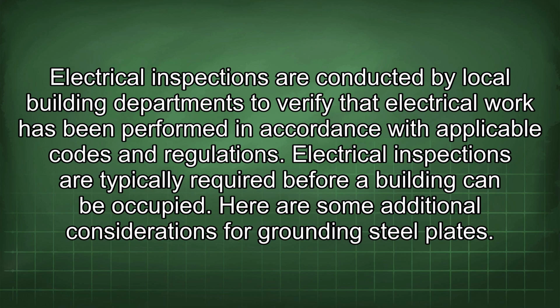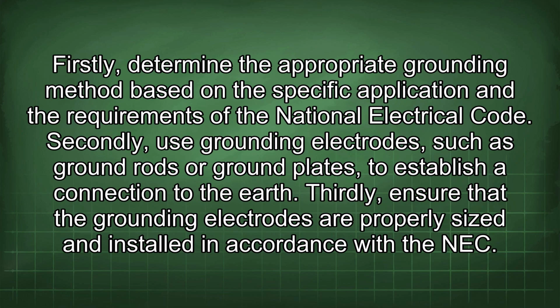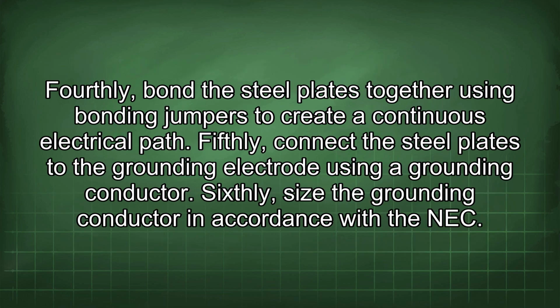Here are some additional considerations for grounding steel plates. Firstly, determine the appropriate grounding method based on the specific application and the requirements of the National Electrical Code. Secondly, use grounding electrodes such as ground rods or ground plates to establish a connection to the earth. Thirdly, ensure that the grounding electrodes are properly sized and installed in accordance with the NEC. Fourthly, bond the steel plates together using bonding jumpers to create a continuous electrical path.